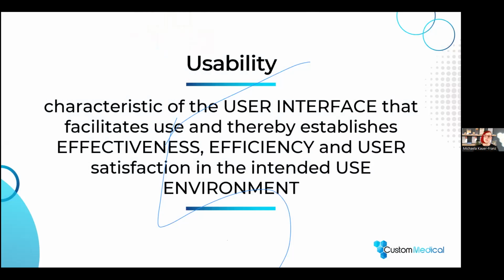And it's also the definition which is referred to from the medical standards. Some words about that. Effectiveness means if a product can do, or if a user can do with the product, what he intends to do. And the second thing, efficiency, is how much effort your user needs to reach his goal. And the third thing, user satisfaction, is exactly what it sounds like. So how satisfied is he with the usage? This is the general usability definition.